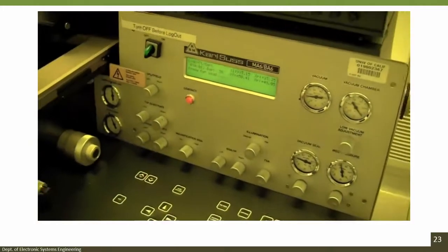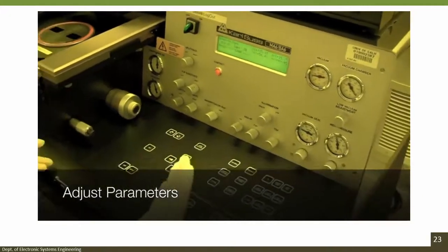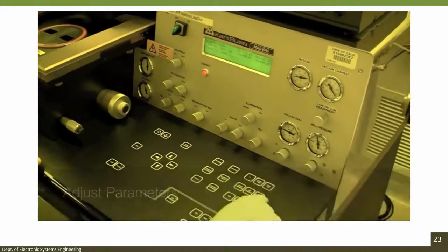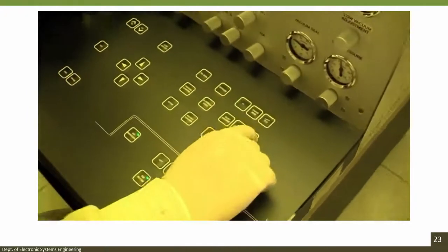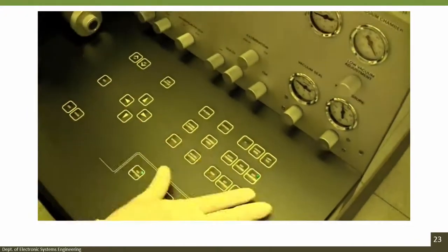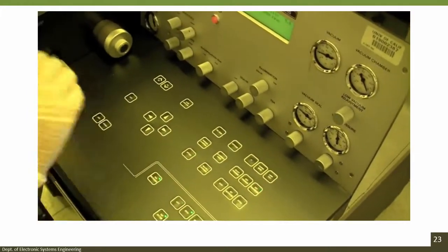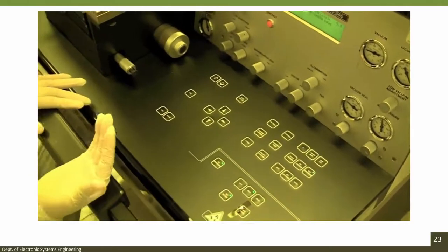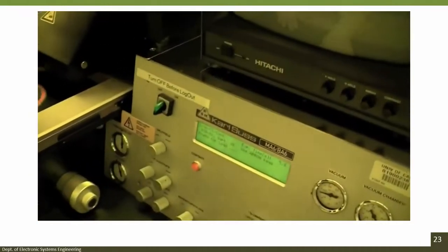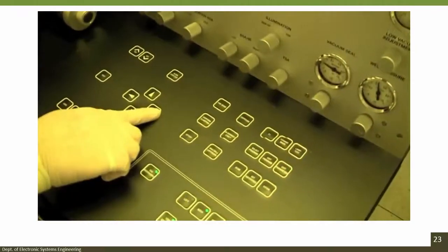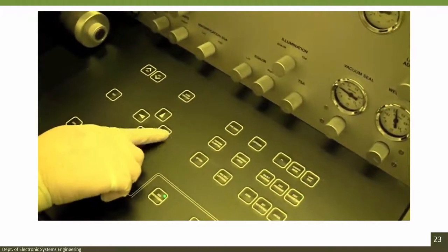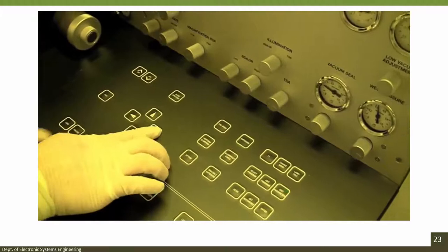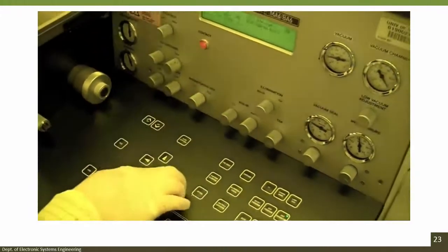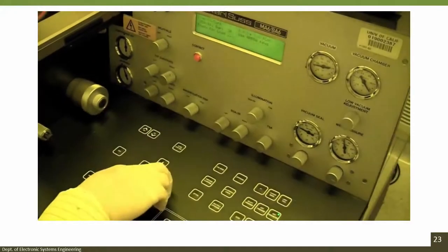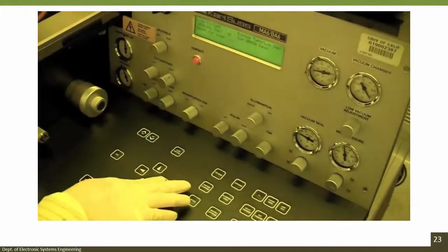Before we run the machine, the one thing we can do is change the parameters. You hit this button called Edit Parameter. Now you can adjust the parameters such as time, gap distance, and type of exposure. How do we change the different parameters? We can use the X left and right. As we move this way, you can change the gap, change the type of contact, and then change the exposure type.